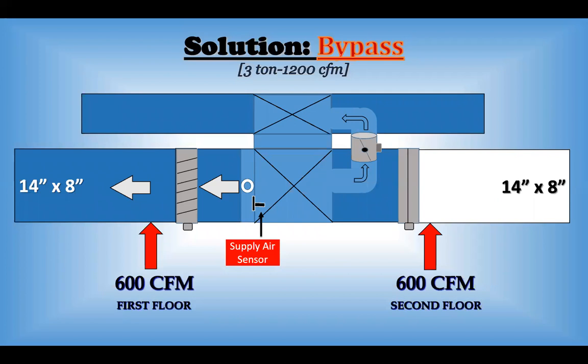Now I want that bypass duct to be the first trunk or the first duct off my plenum. So that has to be prior to any damper, prior to any main trunk line running off that plenum. It is reintroduced into the return air as far away as possible, at least up to 6 feet. And I return that into the system prior to the air filter, and prior to re-entering my air handler furnace. If at all possible, over 6 feet, but 6 feet is acceptable.